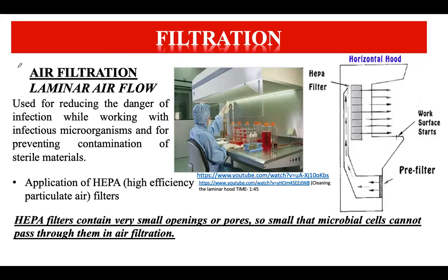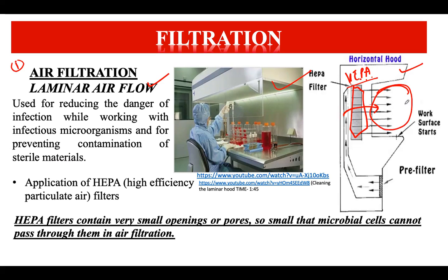An important instrument using the filtration method is the laminar airflow, widely used in laboratories for microbial or other analysis requiring a sterile environment. It has HEPA filters — High Efficiency Particulate Air — attached that filter incoming air, removing all contaminants and microorganisms. The filtered clean sterile air is then circulated in the hood, allowing work in a contamination-free environment.